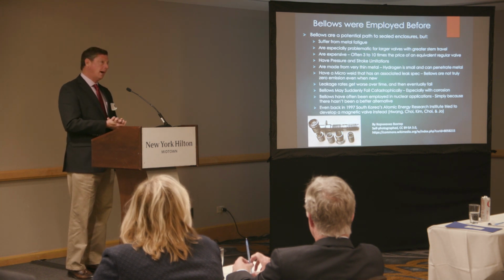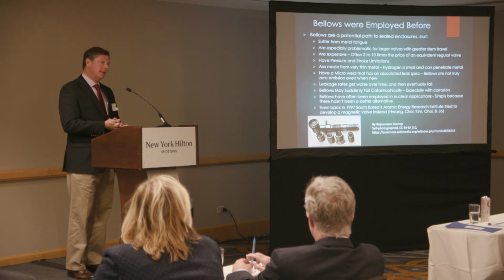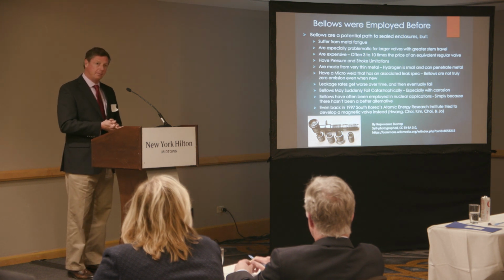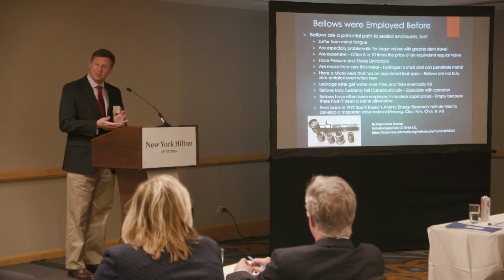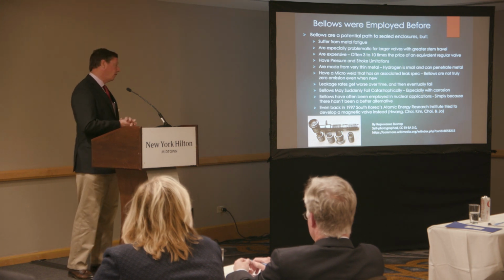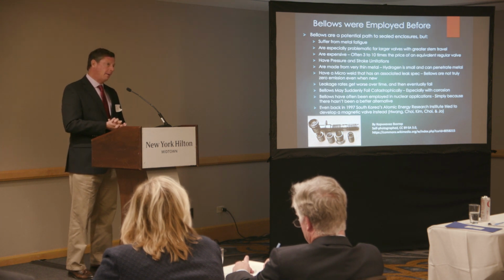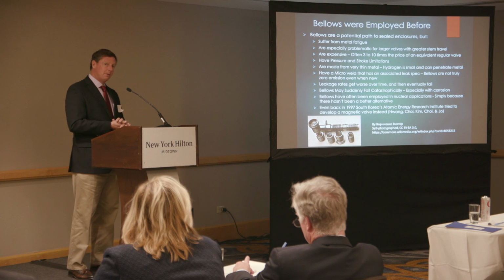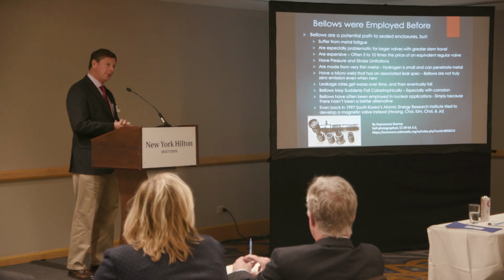The bellows are thin, they flex like an accordion, they fatigue over time. In any macro scale valve, they'll have a welded seal where the sheet metal comes together. That has a leak spec initially, and gets worse over time. They can fail catastrophically, surprise, the whole entire bellows is gone. And for a tiny molecule like hydrogen, hydrogen goes through metal and causes some embrittlement too. With a very, very thin metal like a bellows, that process is kind of on steroids.